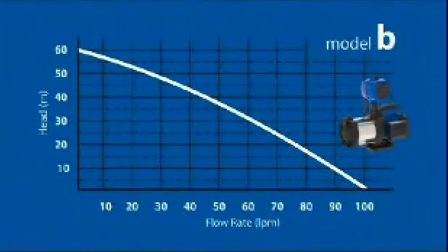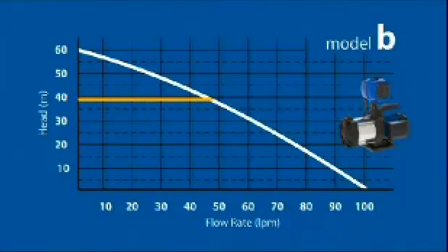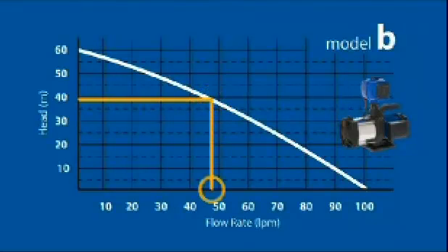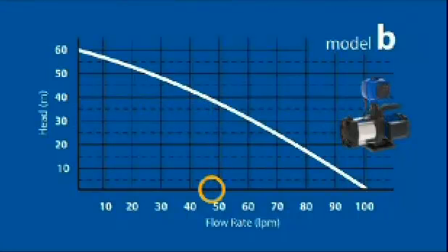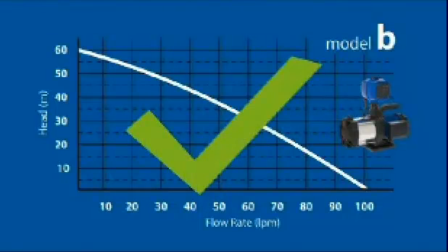Let's try the pump curve for model B. Again, find 39 metres on the head or vertical axis and run an imaginary line across the graph till you meet the pump curve. Then draw a line straight down to the flow rates. Is this pump able to produce the flow rate required at the pressure you require? In the case of model B, the answer is yes. This means model B has both the pressure and flow rate to meet Aunty Flo's needs.